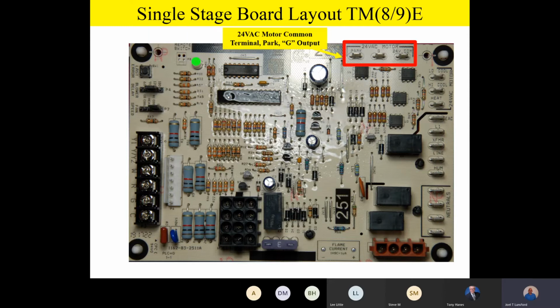As we move around towards the top of the board, you'll notice there's some 24-volt motor terminals. You'll see that there's one that says Park, and then G, where you can actually select a motor speed for a G only call, as per our fan speed jumper that we talked about a little bit ago, and then 24 volt common.